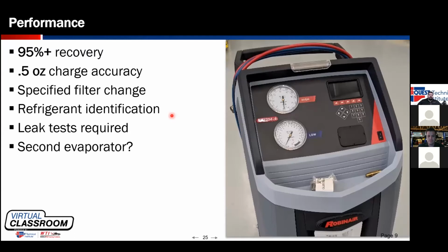Now, half of an ounce to an ounce doesn't seem like a lot, but think about this. How much tighter are we making AC systems today? How much smaller in capacity? I mean, Bryn, what's the smallest AC system that you've seen in your shop off the top of your head? Maybe like 12 ounces. Yep, that's the smallest one that I've seen as well. So if we're thinking about that, a 12-ounce system, what's 1 ounce of refrigerant to a 12-ounce system? That's a 9% charge difference. What's 1 ounce of refrigerant to my Suburban that holds 3 pounds of refrigerant? Nothing. So as we're making the systems tighter and tighter, our charge accuracy has to be better.